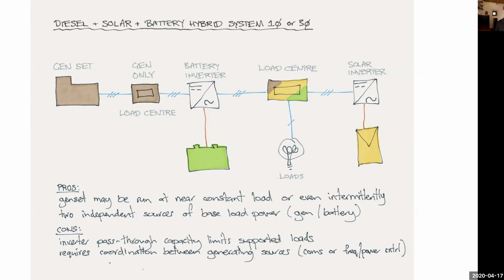You'll be causing a high maintenance cycle on that generating set. But if you add a battery inverter that can charge batteries and supply loads in synchronization with that generating set, it will then run that generating set at the load that's most efficient. You program it into the inverter. So you might choose to run the gen set at, say, 75% of its maximum load, where the fuel efficiency is good and the maintenance cycles are low. Even if the loads are light, it will charge the batteries to maintain that load on the generating set. Or if the loads go up, it'll reduce the charge rate to the batteries and supply the loads.